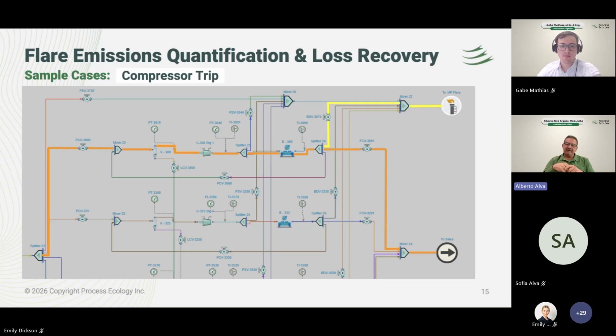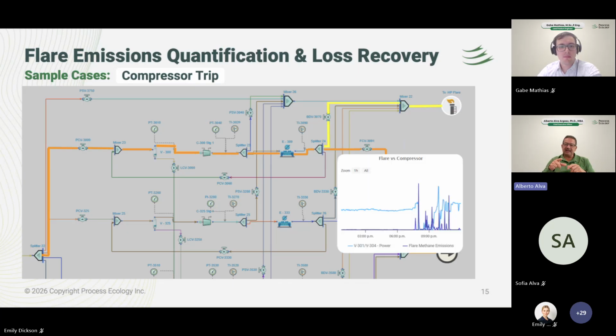And in this particular case I'm describing, in the next chart, you can see that the light blue line is the power to the compressor. Based on pressure differentials and all these things, we're calculating how much power is being used by that compressor engine. And then something happens and the power goes down, so the compressor trips. And then, of course, immediately you see the flare. Nothing new or amazing about this behavior. This is how these systems are designed. It's just the ability to track in real time what's really happening, and why this is happening. In this particular case, based on the correlations that I mentioned before, it appears that some liquid carryover could be the main reason for these compressor trips.